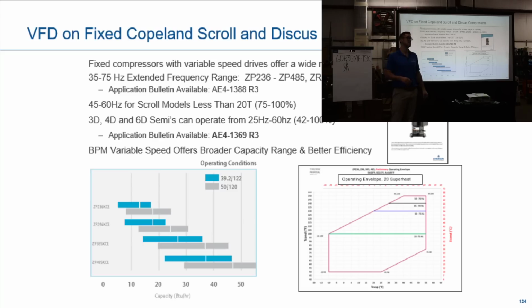Yes, any fixed Discus compressor or scroll can have a drive put on it in the field right now. Fixed compressors with variable speed drive offer a wide range of capacity. That's fixed, so anything in the field right now. Depending on the model, and remember I talked about going to those AE bulletins, you can go from 35 to 75 hertz. So that's down to 46%. That's a lot of capacity.